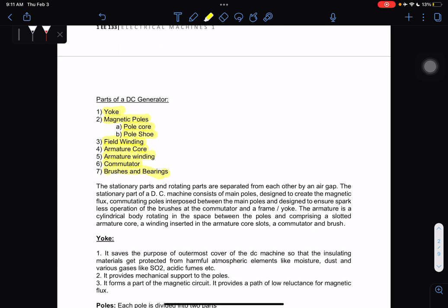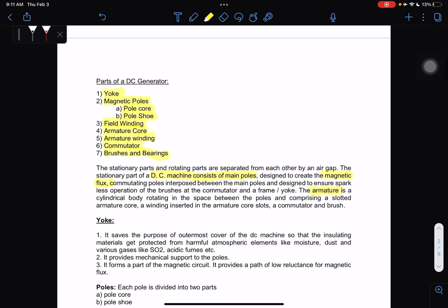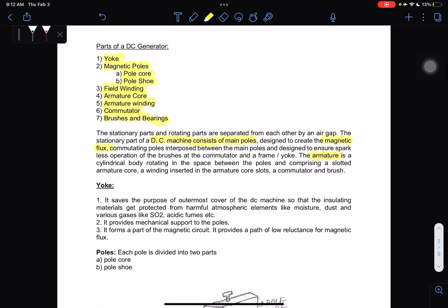The stationary part of a DC machine consists of main poles designed to create the magnetic flux, commutating poles (interpoles) between the main poles designed to ensure sparkless operation of the brushes at the commutator, and a frame or yoke. The armature is a cylindrical body rotating in the space between the poles, comprising a slotted armature core, a winding inserted in the armature core slots, a commutator, and a brush.